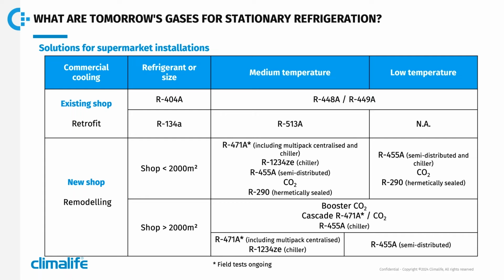For stores of less than 2,000 square meters for medium temperature, we have 471A in centralized system with direct expansion or in chiller. We also have 1234ZE in chiller. And as you know, CO2 in direct expansion or propane in hermetically sealed system. And to finish, we have 455A in direct expansion in a semi-distributed condensing unit. What does semi-distributed mean? This is an independent multi-station unit, simply zoned. For example, we have condensing units that can be charged with up to 84 kg of 455A to supply the various cabinets of the stores. For low temperature, the solutions are 455A, CO2 and propane.